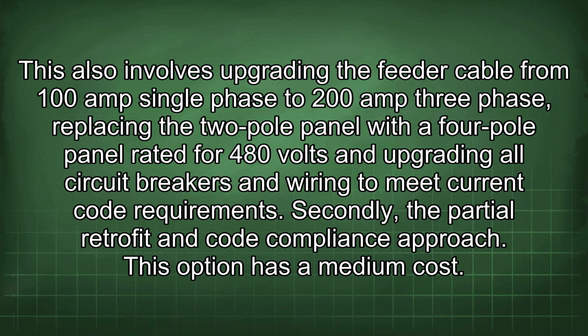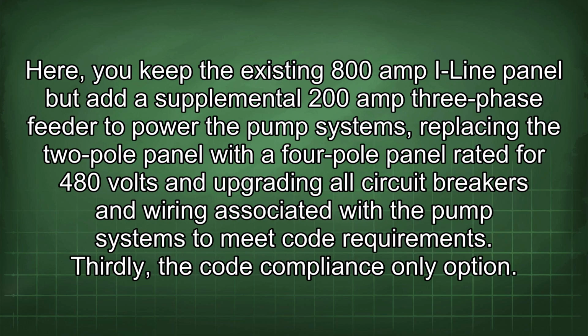Secondly, the partial retrofit and code compliance approach. This option has a medium cost. Here, you keep the existing 800 amp I-Line panel, but add a supplemental 200 amp three-phase feeder to power the pump systems, replacing the two-pole panel with a four-pole panel rated for 480 volts and upgrading all circuit breakers and wiring associated with the pump systems to meet code requirements.